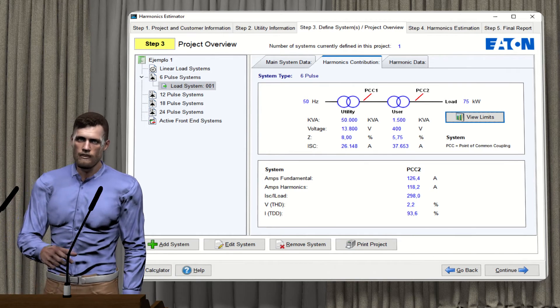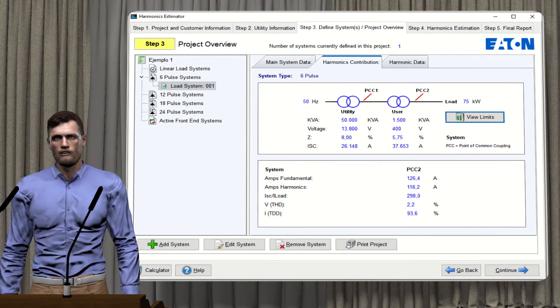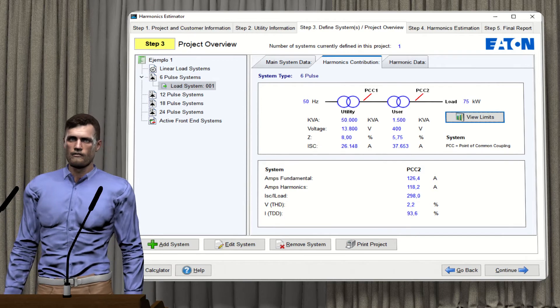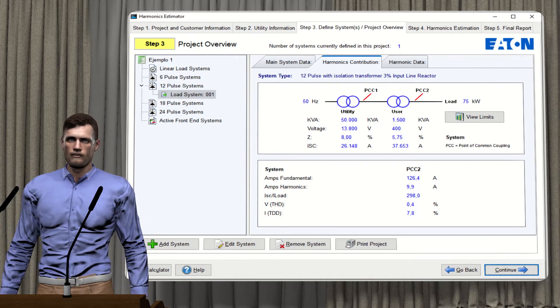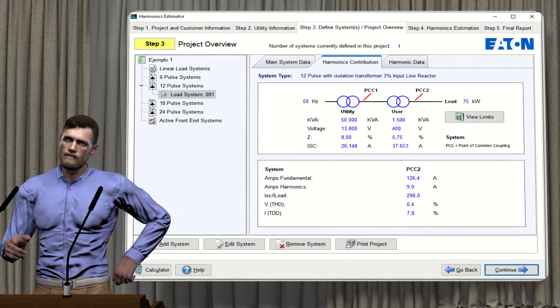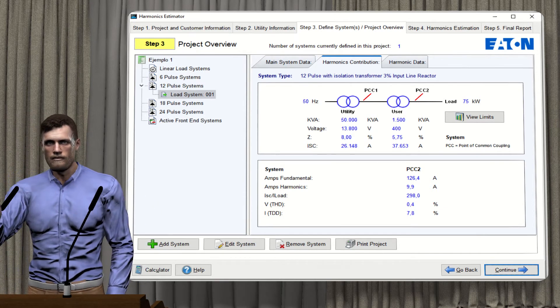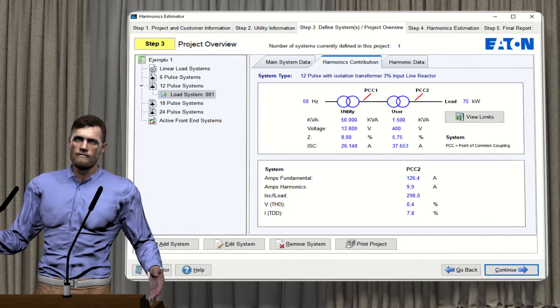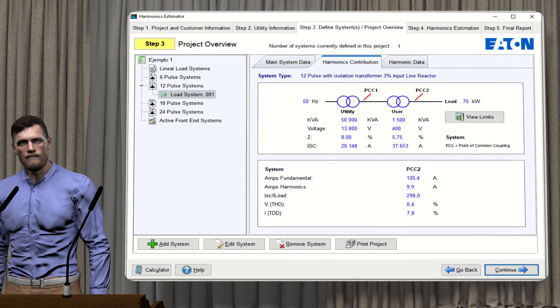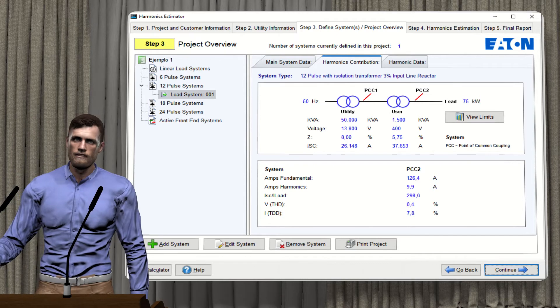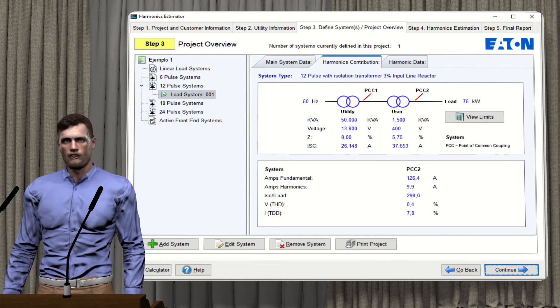For a variable speed drive with a 12-pulse input rectifier stage, the THD values would be around 0.4% for voltage and 8% for current, according to this harmonic calculation software. As we can see, going from a rectifier input stage from 6 to 12 pulses implies a substantial improvement in the current THD value, and as a consequence of the voltage THD.